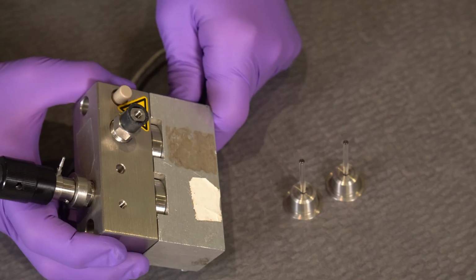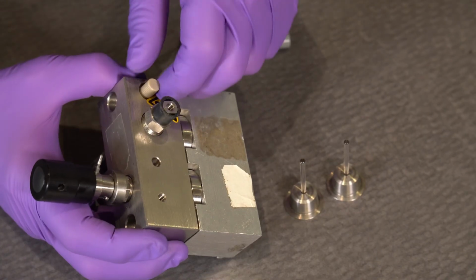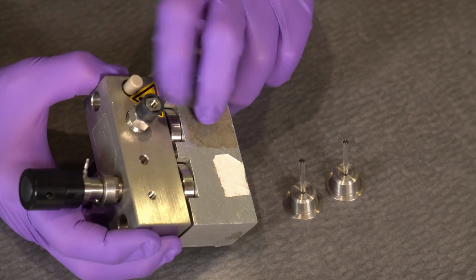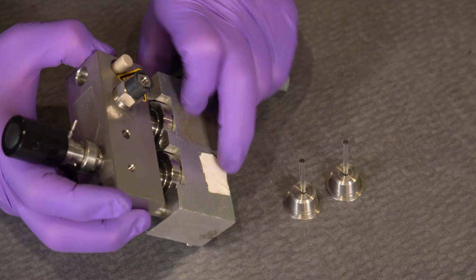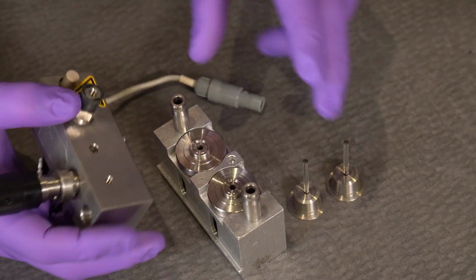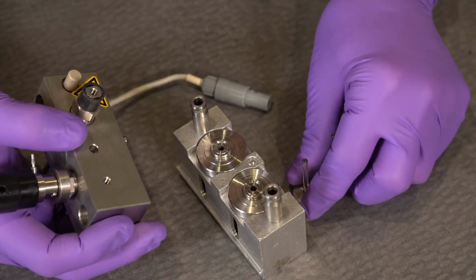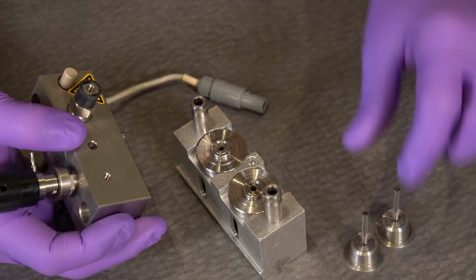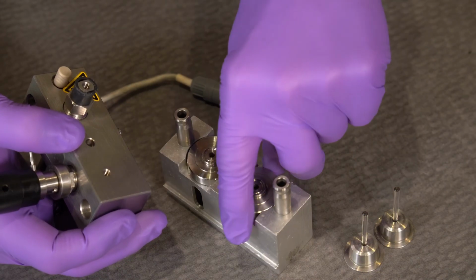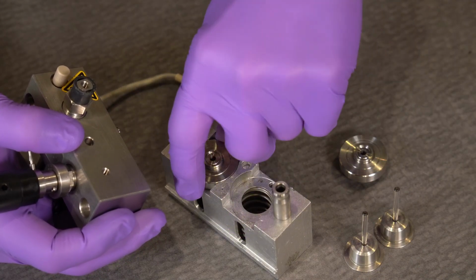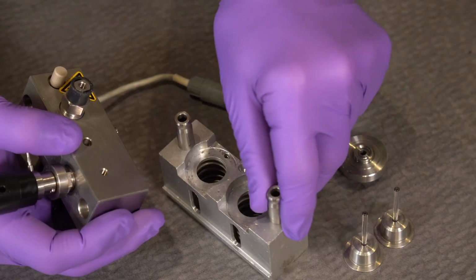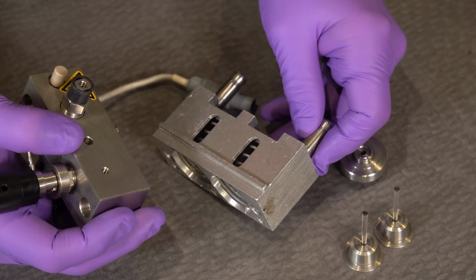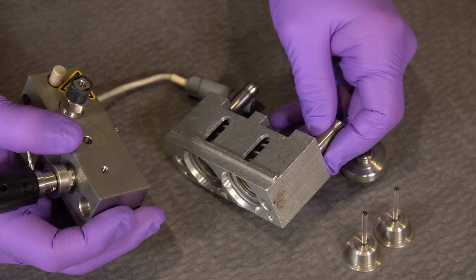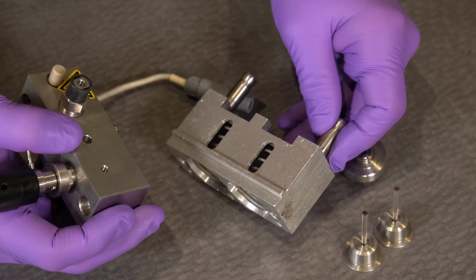So the next step is to remove the two parts of the pump head, and that's just a loosening screw. So when we release the two parts, on one side, we have the little piston rings, the little guides to make sure the pistons go straight. And then inside there, you'll see a spring, a couple of springs. I always check those springs, make sure they're not corroded.